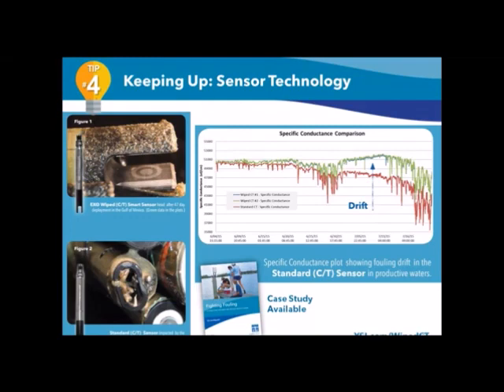Now, in this case, we tested the new wiped conductivity probe against our standard probe, and we wanted to get data that really demonstrated the effectiveness against intense sensor fouling that we've talked about here. The new probe is in green on the chart here. The standard probe is in red, and that does not have the wiping capability. So the standard probe actually began to see signs of artificial data drift in the first week or two, just due to fouling accumulating on those electrodes. And the wiped probe, as you can see here, continues to collect pretty good quality data over the course of the month-long deployment.